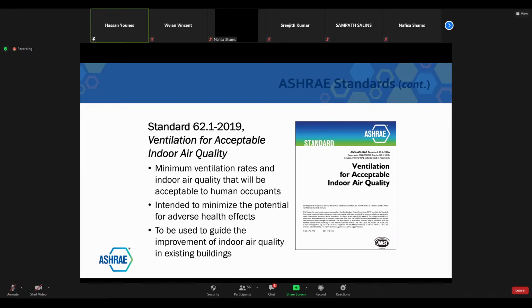So there are some requirements on the way you maintain your equipment as well. Drain pans on the cooling coil, so you know that the cooling coil will start condensing that moisture and removing it from the airstream because you want to reduce the humidity in the room. But that water should not be stagnant, and it should be taken out from the drain pan, because water will allow bacteria to build, and this is something we don't want.